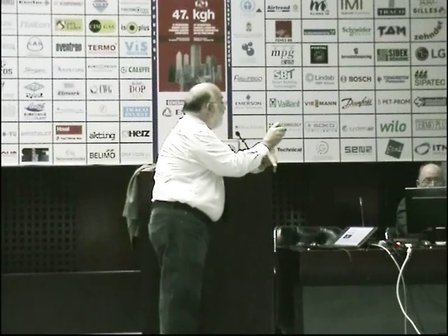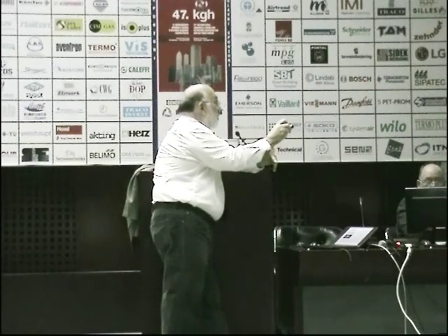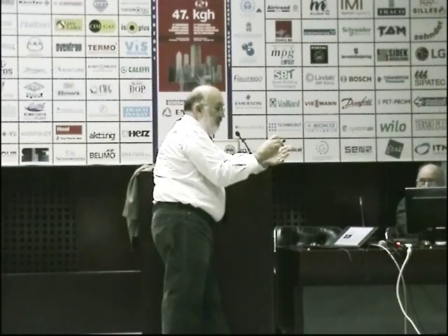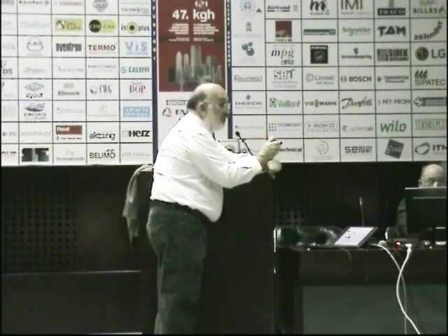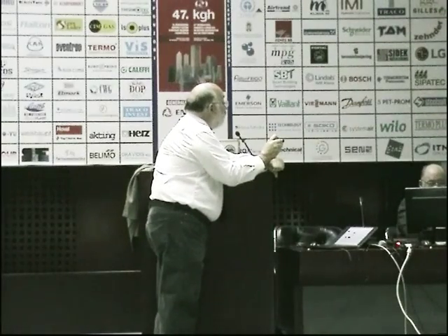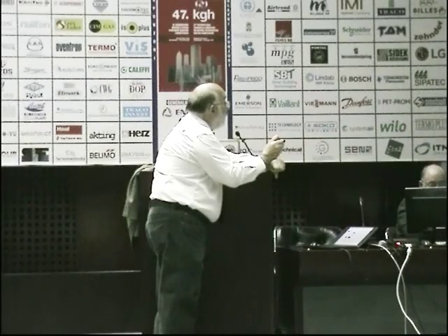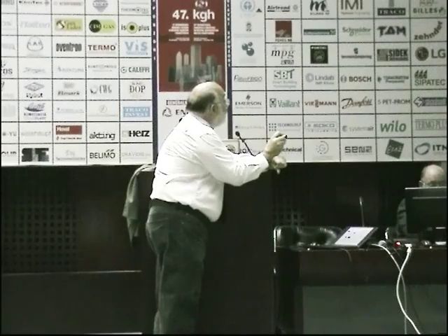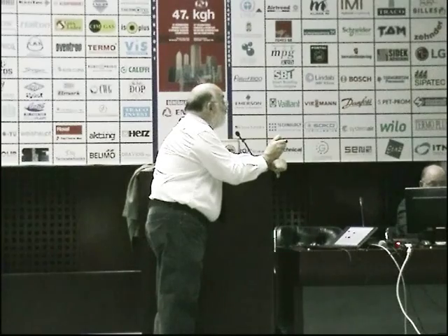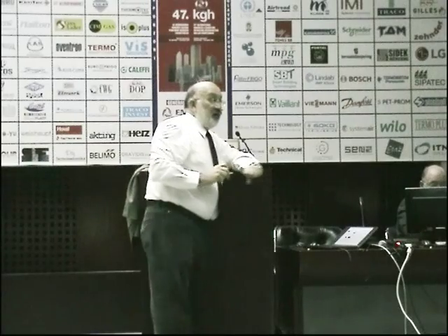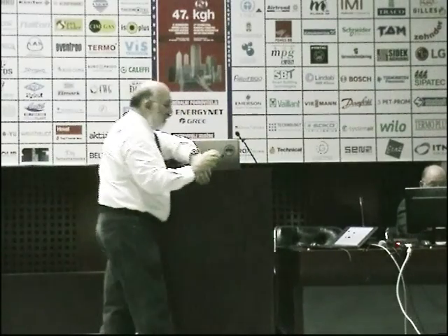Now, of course, you will get some diameter, and you can make a model, but then, of course, you need to calibrate that. That is the tougher part. This is how we have done calibration. With the same camera, with a laser pointing, we made the half of a tube and then a full tube, putting the oil in, shining the laser here, and then with a micrometer going down and measuring the actual thickness, and then related this actual thickness to the diameter of the ellipse.